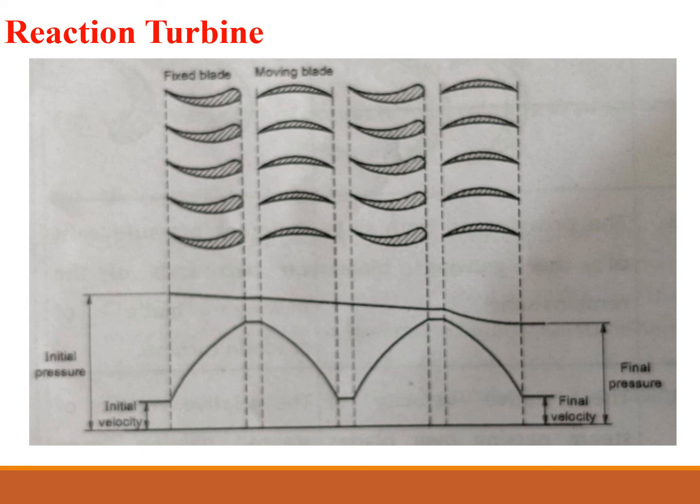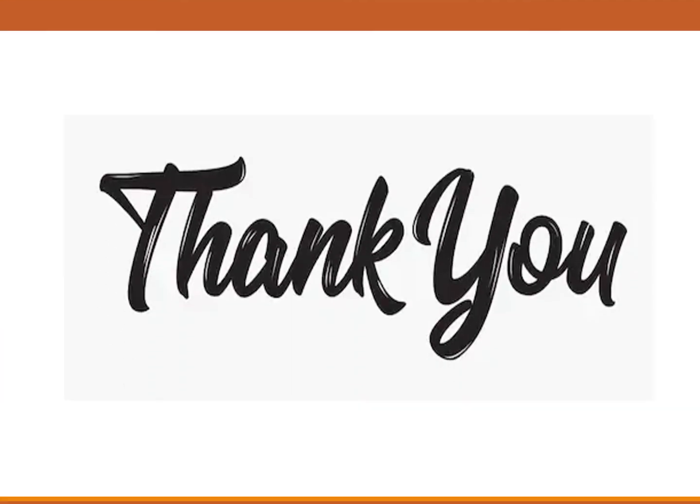A pressure drop occurs across both the stator and the rotor, with steam accelerating through the stator and decelerating through the rotor, with no net change in steam velocity across the stage but with decrease in both pressure and temperature, reflecting the work performed in driving the rotor. Thank you.